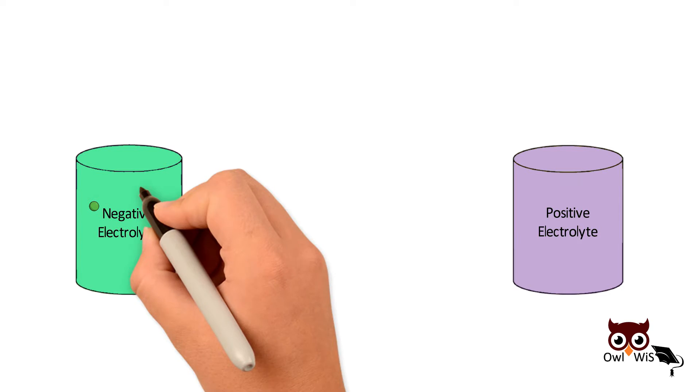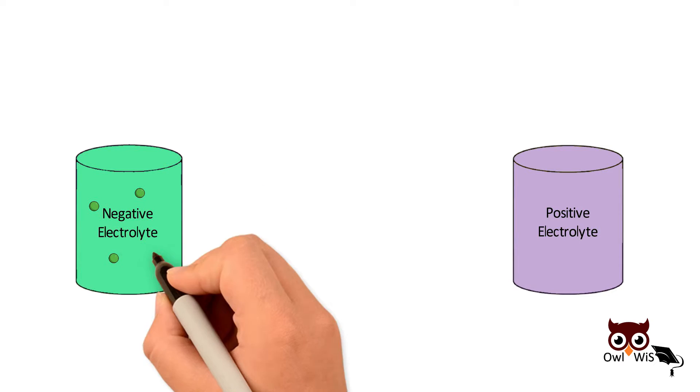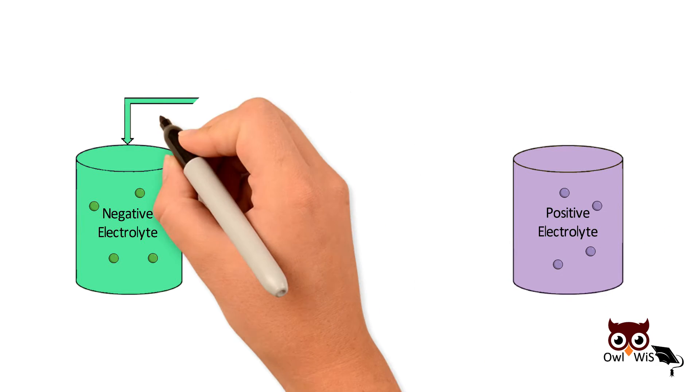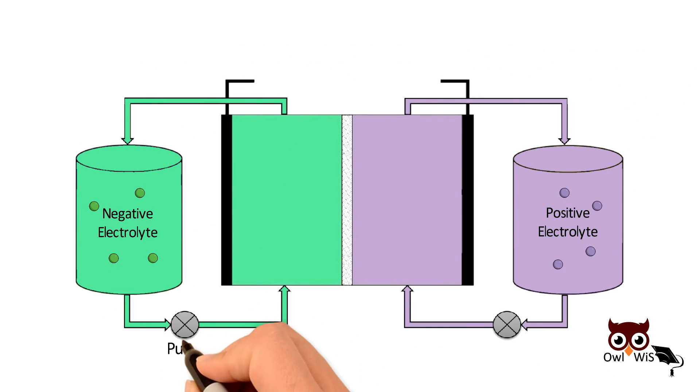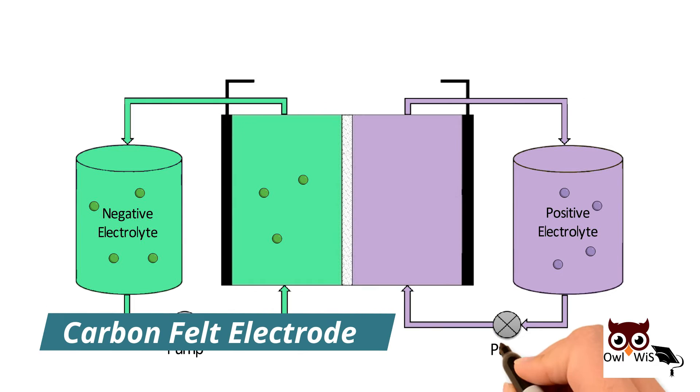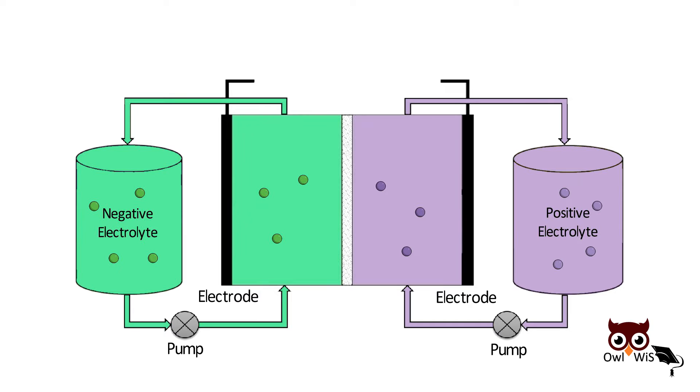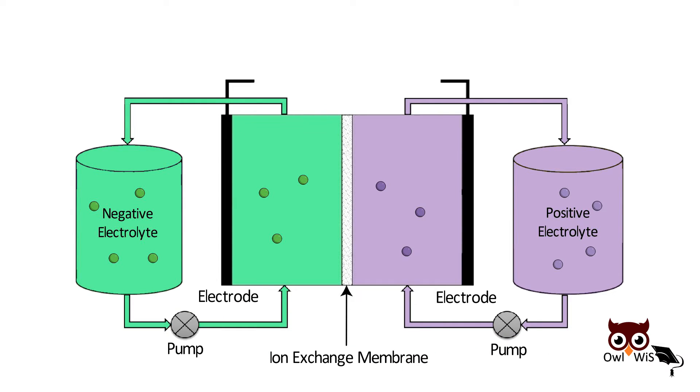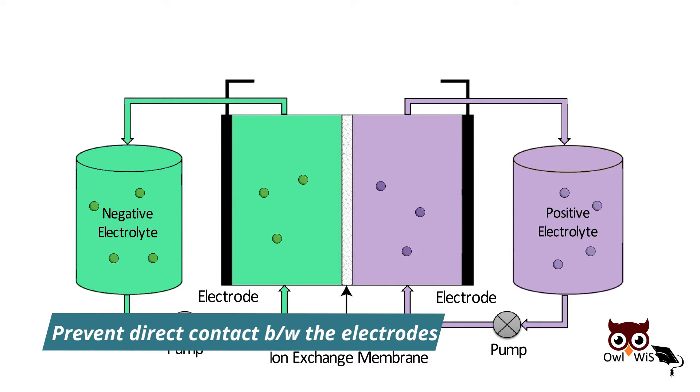Each electrolyte contains dissolved electroactive materials that electrochemically react to release or store electrons. Pumps are used to circulate the two electrolytes through separate carbon felt electrodes that provide abundant surfaces on which the active species can react. The electrodes are separated by an ion exchange membrane that allows only ions to pass through it and prevent direct contact between the electrodes.